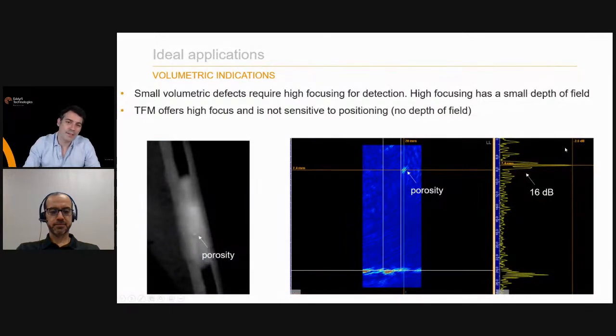Well, I would say the ideal applications, obviously we can use TFM for a lot of applications, are volumetric indications. When we are looking for very tiny indications, we really need to focus on that indication to have maximum sensitivity. But typically when we use high focus, be it conventional or phased array, we have a very small beam, but we tend to have a very small depth of field. So it becomes very, very sensitive to positioning. The advantage of TFM is that we have this high focusing within a region of interest, and we are not sensitive to positioning. We have no depth of field problem.